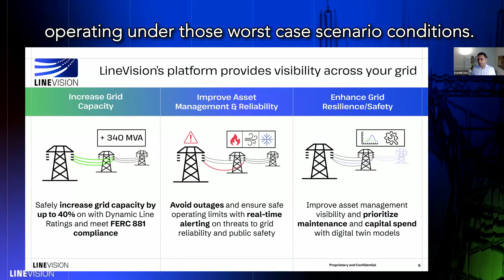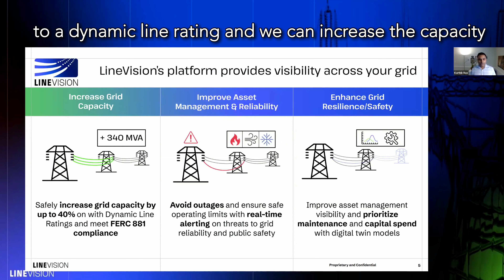By bringing in real world, real time data on ambient weather conditions and the way the line is being operated, we can provide the operator with real time understanding of the true carrying capacity of that line. By doing that, we move from a static line rating to a dynamic line rating, and we can increase the capacity of that line by up to 40% or more.